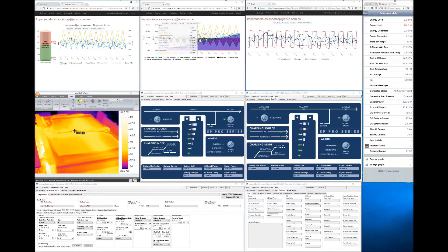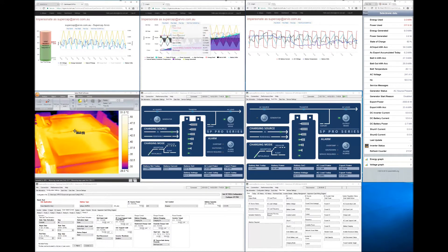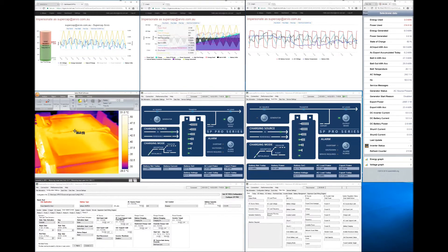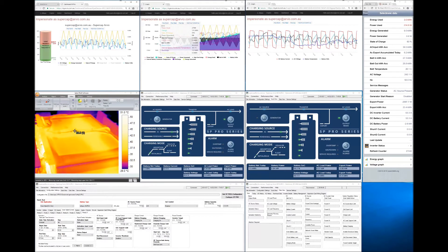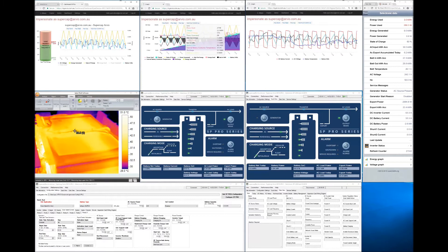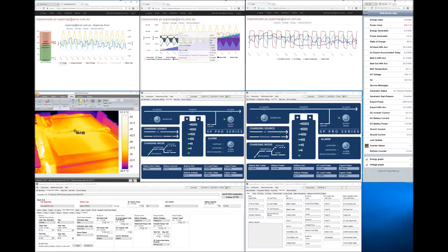So we're basically looking at roundtrip efficiency in this graph. We found that over a period of about a week we lose around about 2% in each direction from a charge and a discharge when we're running at a full nameplate rating of around about 100 amps each way. That's less if we run it at a lower rate. And all of the energy we're losing is coming in as heat.